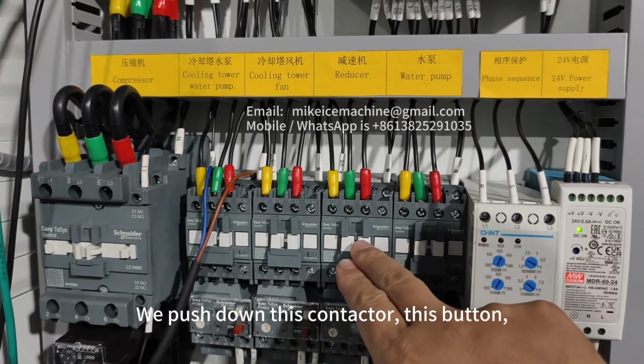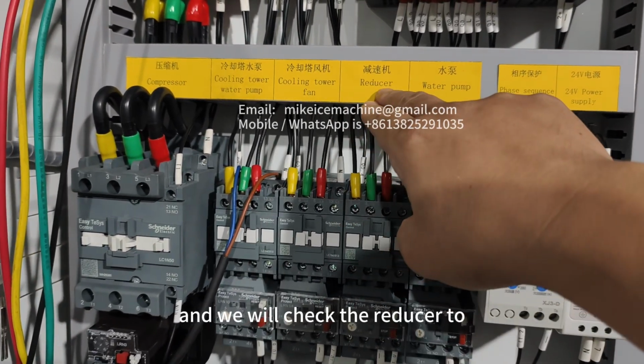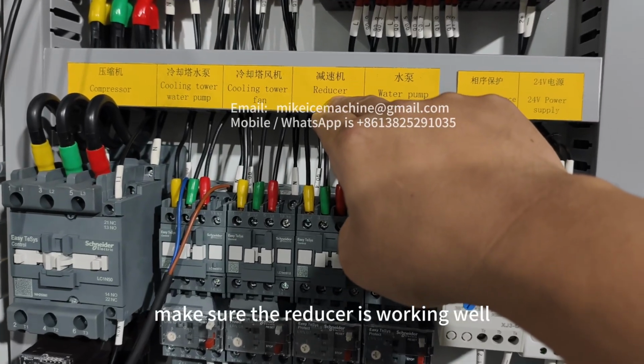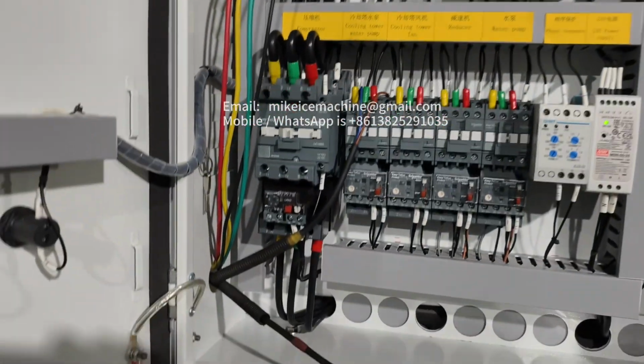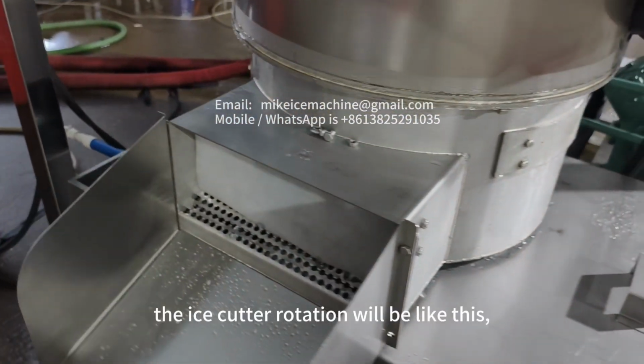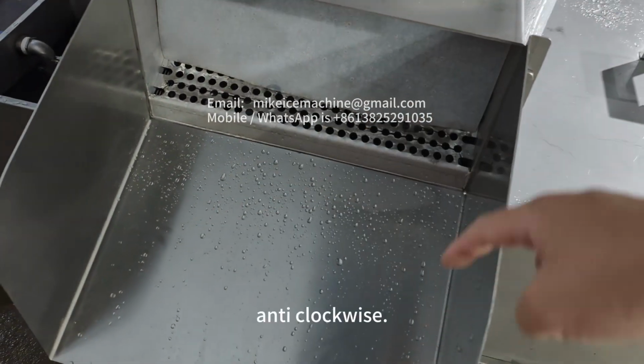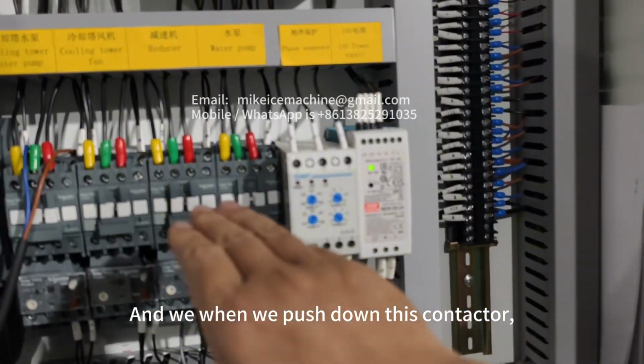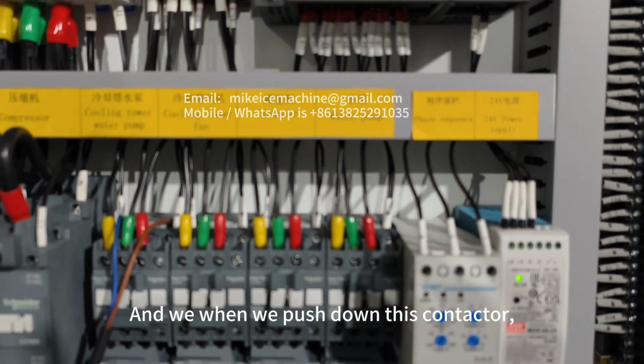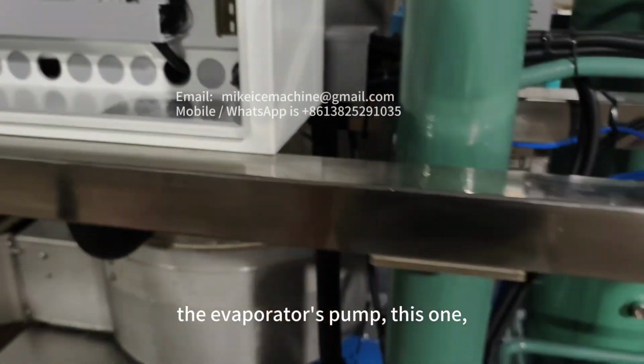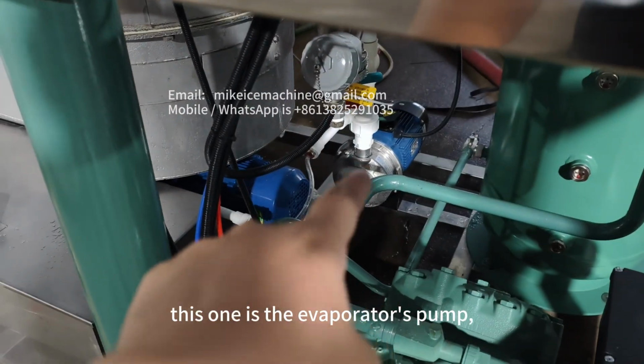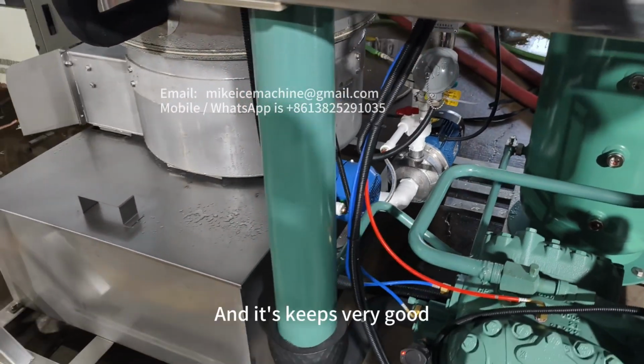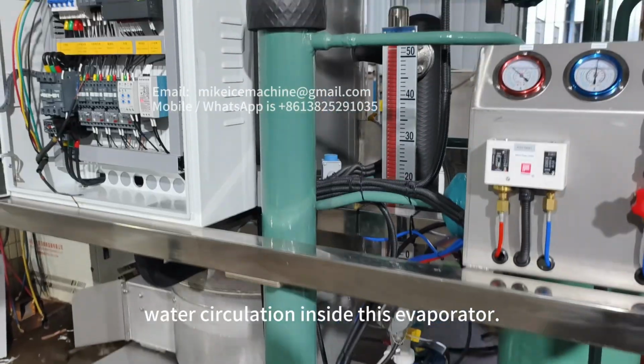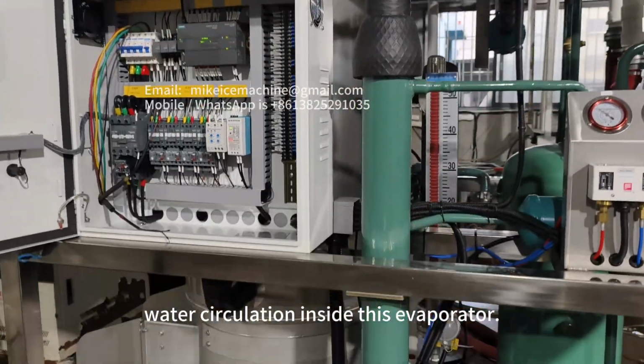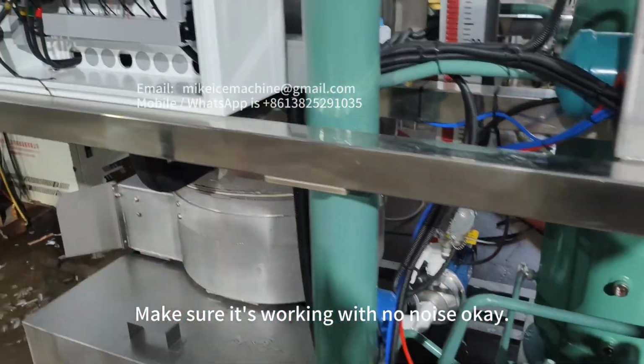We push down this contactor, this button, and we will check the reducer. Make sure the reducer is working well with the correct rotation. Normally, the ice cutter rotation will be like this, anti-clockwise. Okay. And when we push down this contactor, we should check the evaporator's pump. This one is the evaporator's pump. It should be working well, and it keeps very good water circulation inside this evaporator. Make sure it's working with no noise.